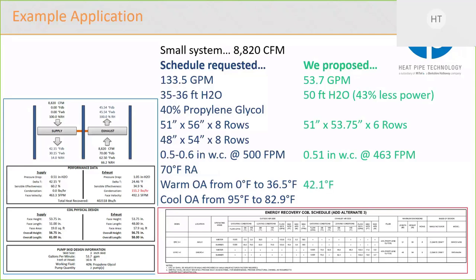So in the winter, we were hitting 42.1 Fahrenheit, so we exceeded the goal, and presumably we were designing to the summer condition because we got very close to the summer condition, which was 82.9. So hopefully that gives you a good idea of how we're different, how we can meet existing performance, but do it consuming less power by the pumps.